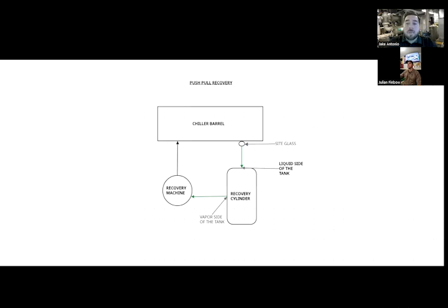So if you're looking at this diagram now, the reason why we call it push-pull is because we're pulling refrigerant off the top of the recovery cylinder. So we're causing a low pressure to happen in our recovery cylinder. We're utilizing our recovery machine as a pump to add pressure to our chiller. So we're pushing vapor into our chiller and we're pulling the liquid out. So the liquid is going right into the recovery cylinder. And what happens is you can kind of do this until all of the refrigerant is out of the chiller, and we're just going to be circulating vapor throughout the chiller and the cylinder and the recovery machine.